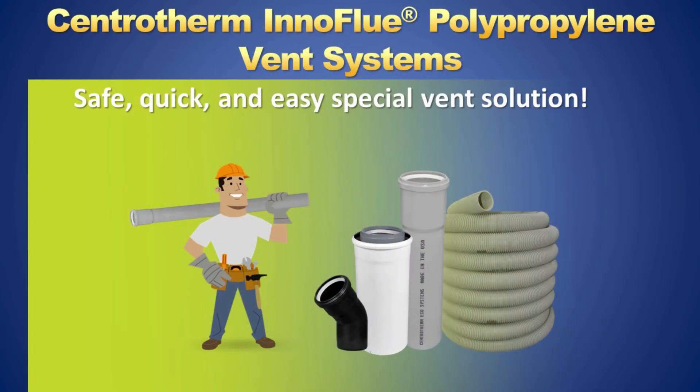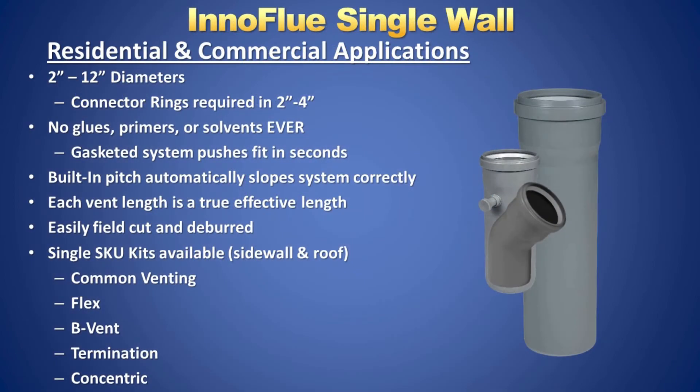Centrotherm manufactures the InnoFlue brand of polypropylene, which is the only brand listed for use with oil flue gas. It is tested and approved for temperatures of up to 248 degrees Fahrenheit. InnoFlue is a single-wall, gasketed vent pipe connected with locking rings. The 87-degree elbows are at a pitch which maintains the proper 1/4 inch per foot requirement, and the vent lengths are true effective lengths. There are no glues or primers, and it is quickly and easily cut and deburred.